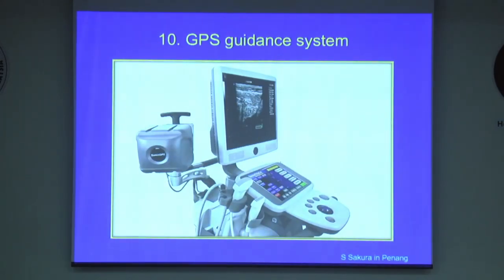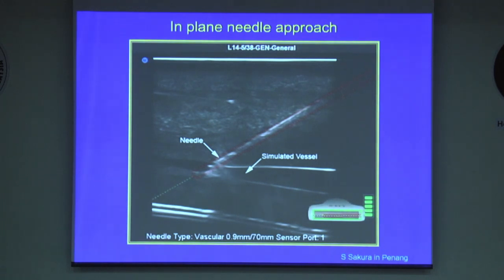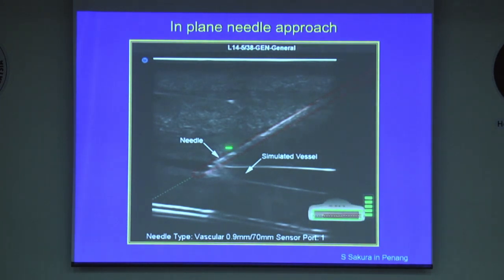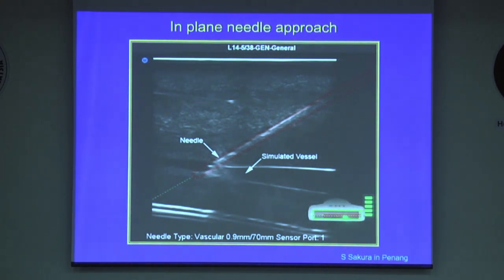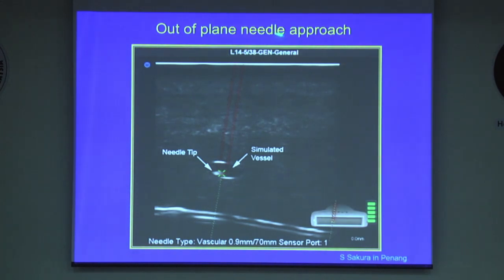Finally, there is another technology that some ultrasound companies have started to offer: a GPS guidance system. This slide shows an in-plane ultrasound image view with a GPS system. The technology provides information on the needle location, indicated by a red silhouette with the projected path in green. On the bottom right, you can see the footprint of the transducer with the relative needle position. This works with out-of-plane technique as well.